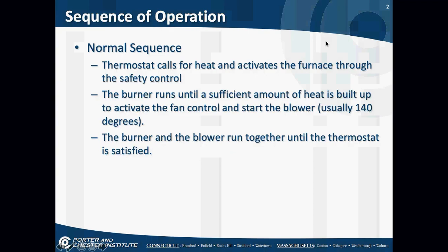Burner operation, normal sequence of operation. The thermostat calls for heat and activates the furnace through the safety control. The burner runs until a sufficient amount of heat is built up to activate the fan control and start the blower. That's usually about 140 degrees.